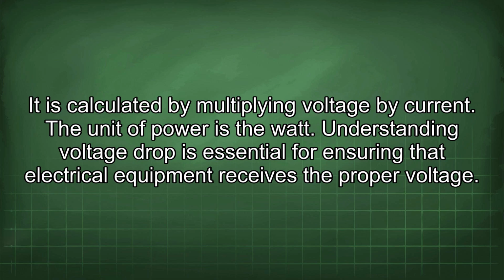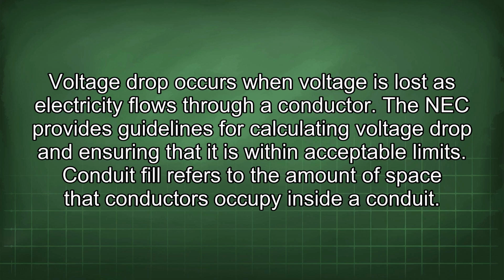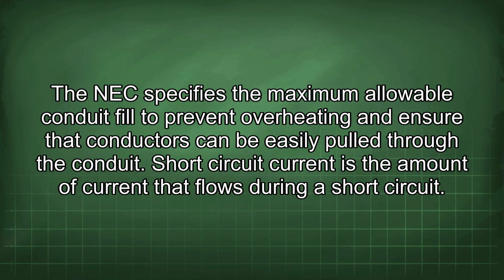Understanding voltage drop is essential for ensuring that electrical equipment receives the proper voltage. Voltage drop occurs when voltage is lost as electricity flows through a conductor. The NEC provides guidelines for calculating voltage drop and ensuring that it is within acceptable limits. Conduit fill refers to the amount of space that conductors occupy inside a conduit.